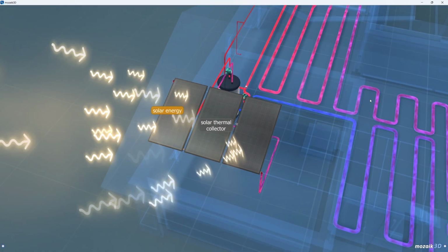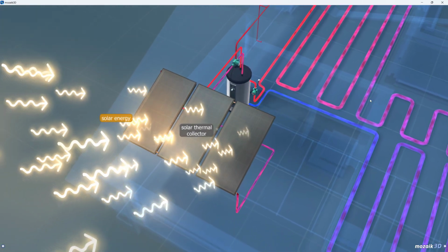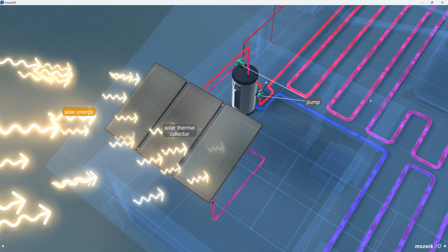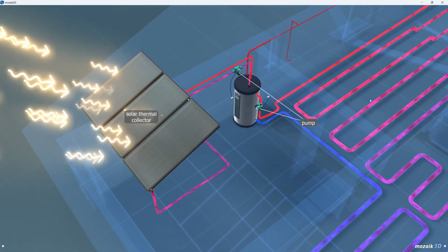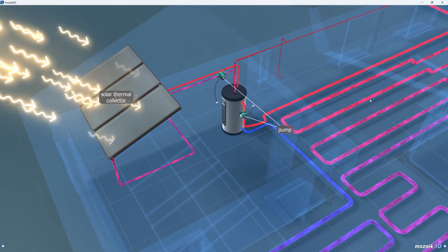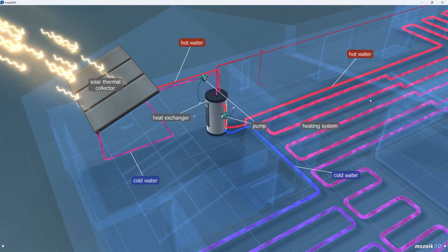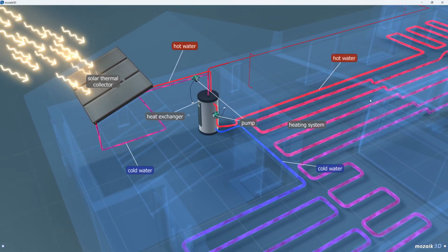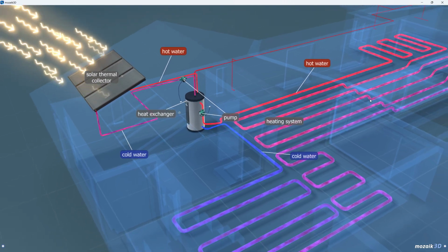Solar thermal collectors form a pipe system with a large surface and with a pump that circulates water mixed with antifreeze. Antifreeze is necessary because the solar thermal collectors are situated outdoors, so their temperature may fall below 0 degrees Celsius in winter. Antifreeze is not necessary in the indoor water loop, so it is important to have a separate closed water loop to be heated by the sun.